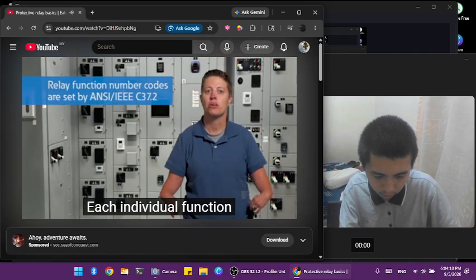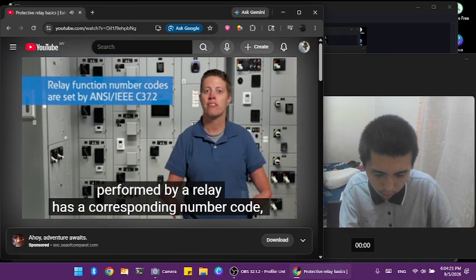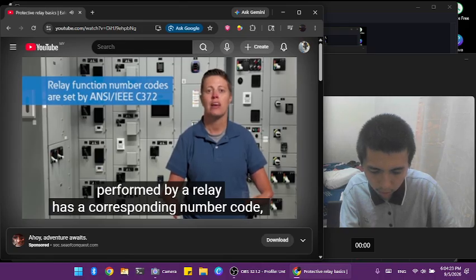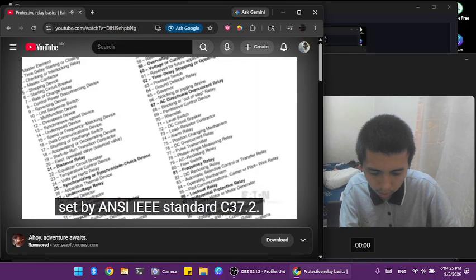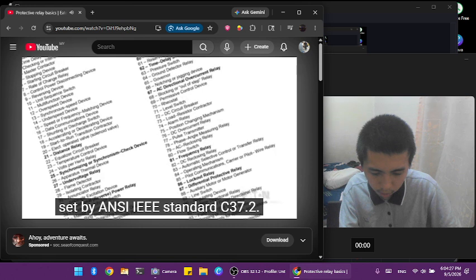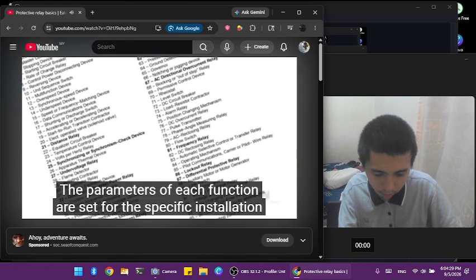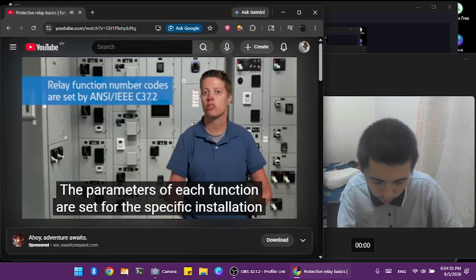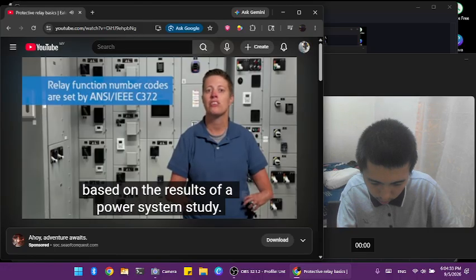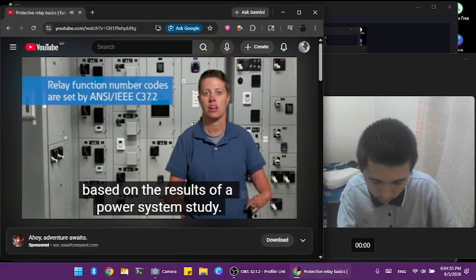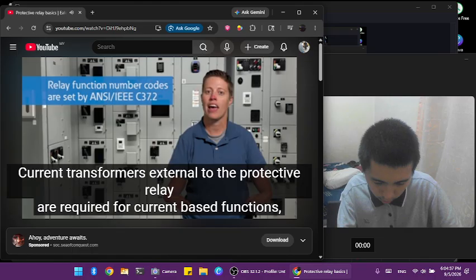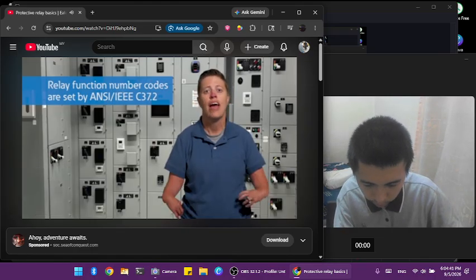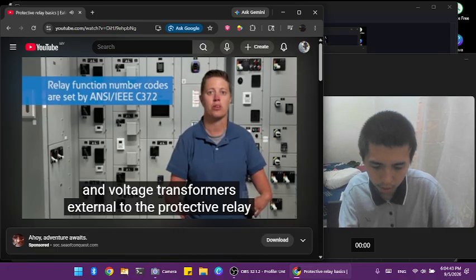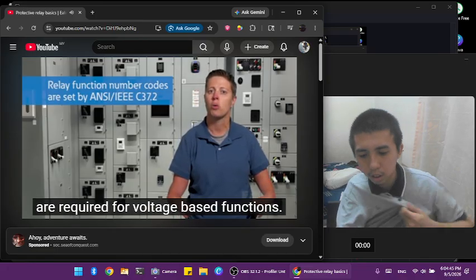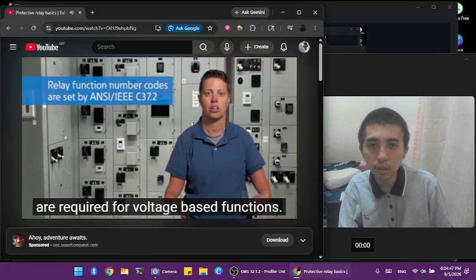Each individual function performed by a relay has a corresponding number code set by ANSI IEEE standard C37.2. The parameters of each function are set for the specific installation based on the results of a power system study. Current transformers external to the protective relay are required for current-based functions, and voltage transformers external to the protective relay are required for voltage-based functions.